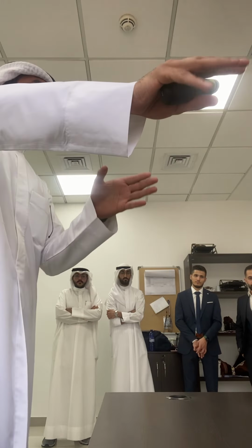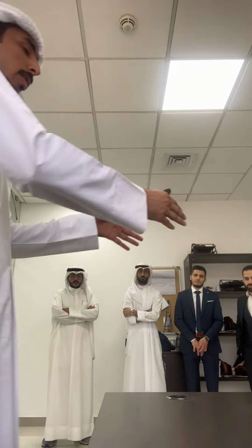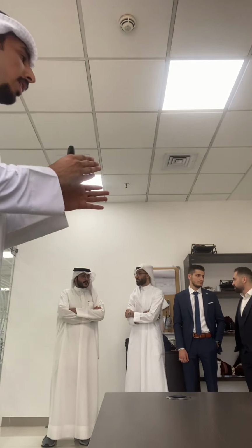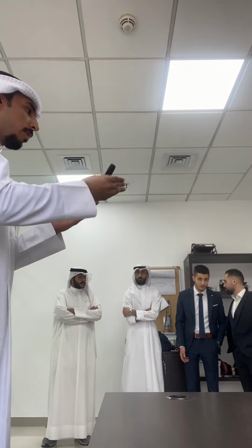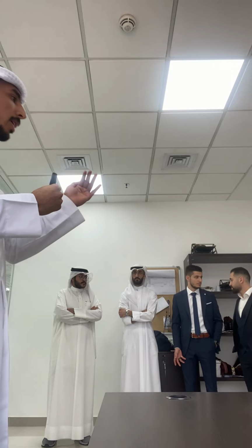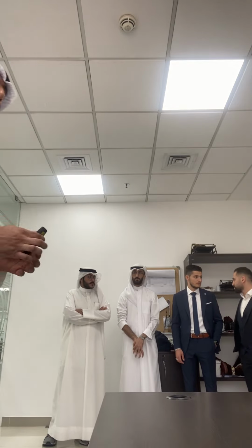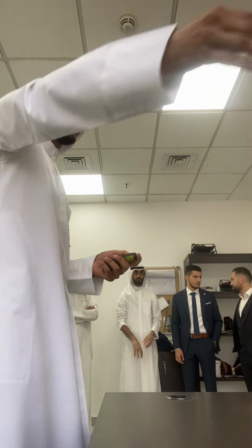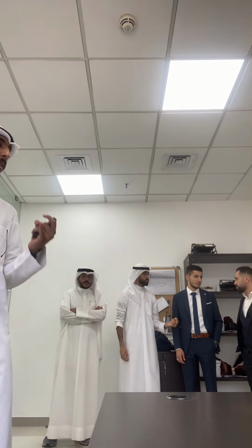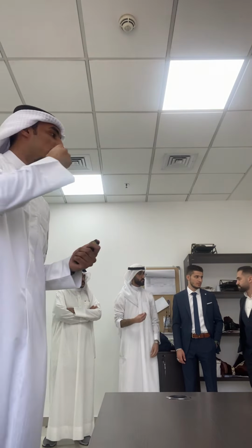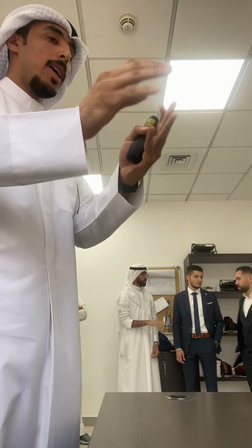As you can see, we have occupants, which is the number of people, and the sensible heat gain. So when someone is sleeping, he gives less sensible heat than one who is teaching or explaining. Then we have the lighting, as I said, it depends on how many lights and the type of light, and all of these numbers we took from ASHRAE standards.